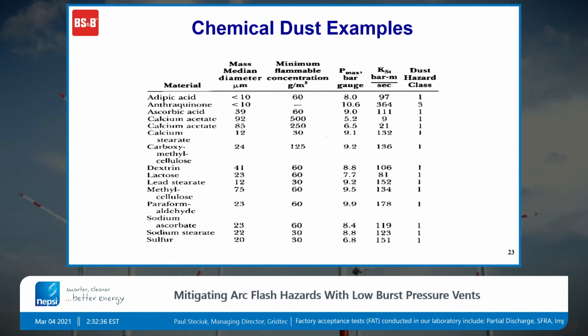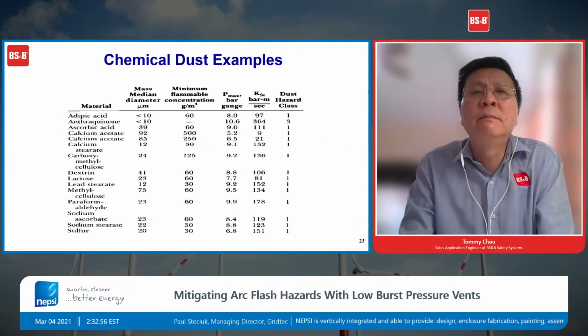So the idea is to put an explosion vent on there at 1 to 1.5 psi and have the explosion vent activate, versus having your equipment see the Pmax value, which could be 100 times the pressure of the explosion vent itself. So that's the idea of having an explosion vent.